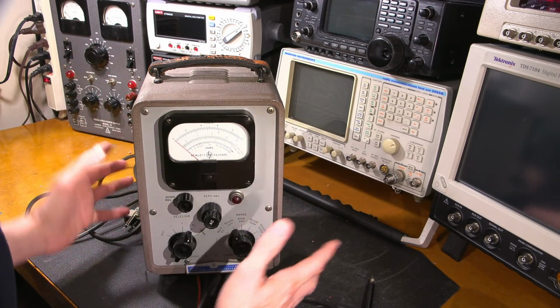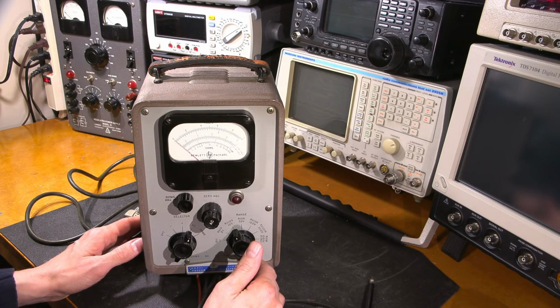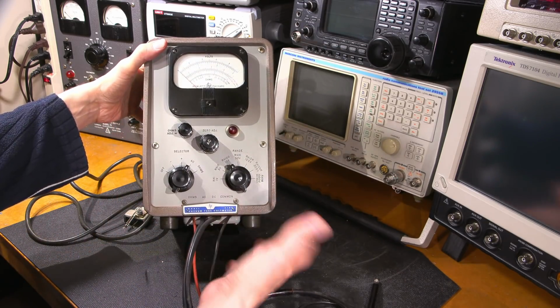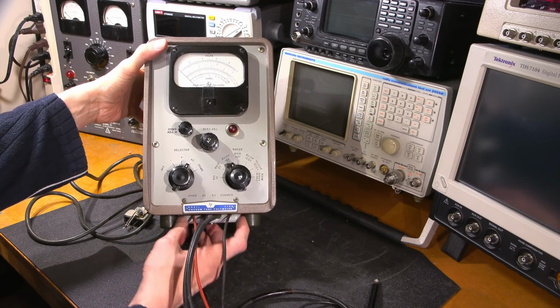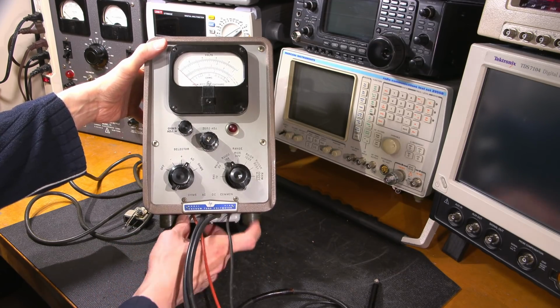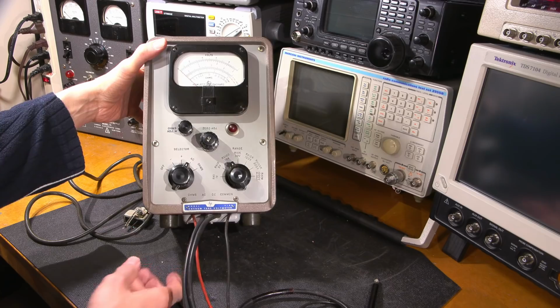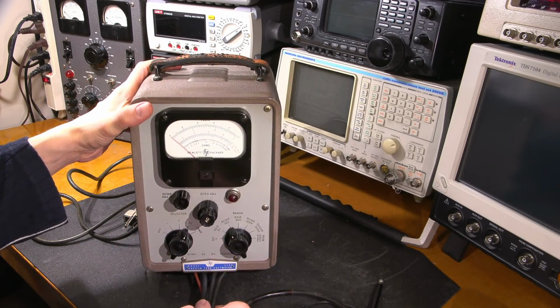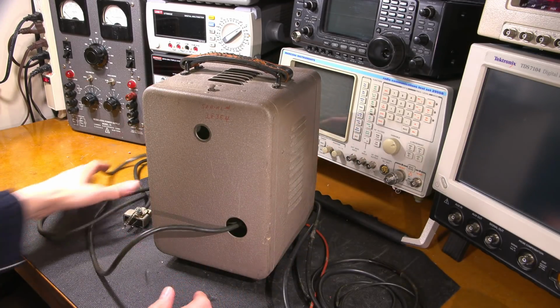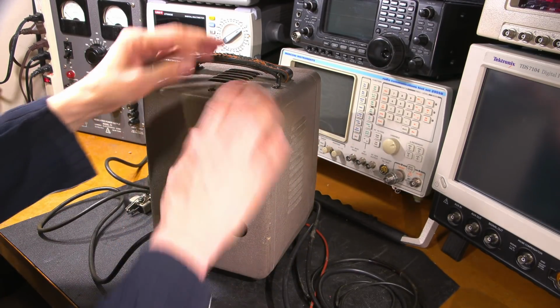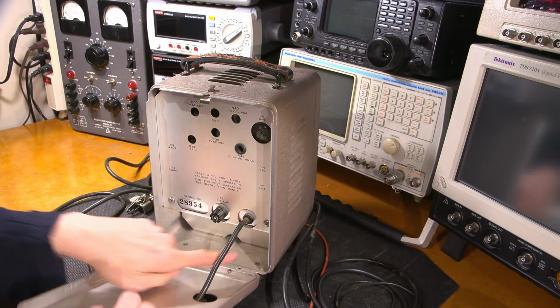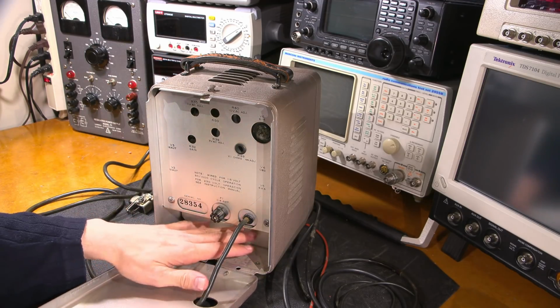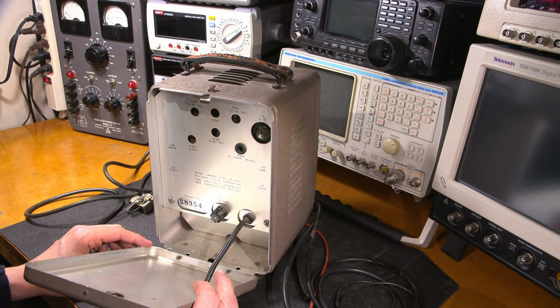But most of the time, I find that these things sit on the bench all the time. So it's a good idea, once you put this on, just leave it on. You don't want to put extra wear on the unit by taking this off and putting it on and taking it off. It's just hard on connections and everything like that. So I find that I leave them all connected. On the back side, you can see the line cord coming out of the back. You can store the probes in the back if needed, down in here with the line cord. It's a little bit tight, but everything fits in there.